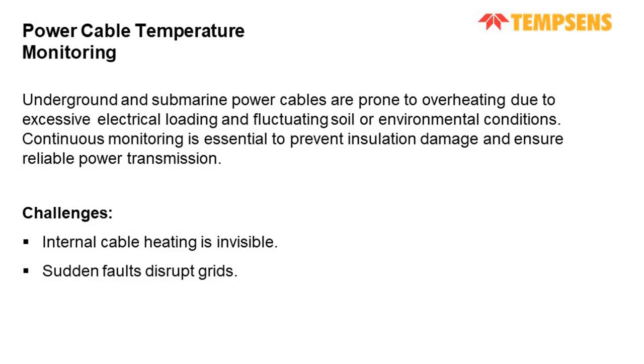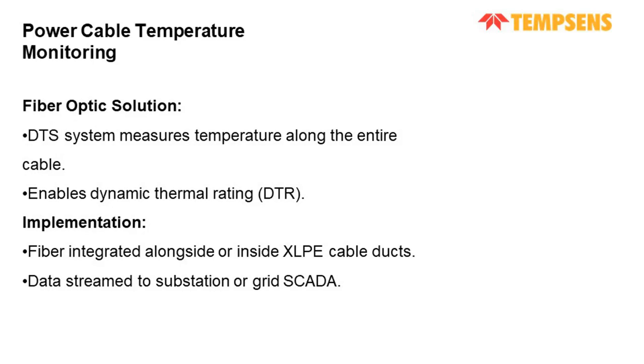So modern electrical grids rely heavily on underground and submarine XLPE cables. Overloading, aging, and changing soil or seabed conditions can cause thermal buildup, leading to insulation failure. And with fiber optic DTS installed along or inside the cable sheath, utilities can monitor temperature at every point along the cable in real time. And this data allows for dynamic cable rating, DCR, where operational limits are adjusted based on the actual condition instead of conservative estimates based on calculations. So fiber optic technology can be used to improve the safety and efficiency of underground and submarine power cables.